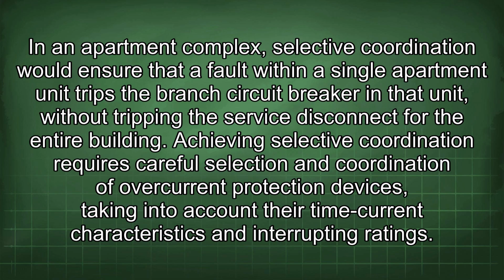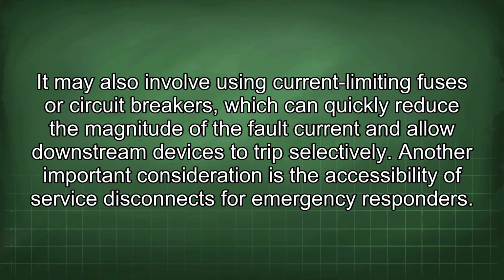Achieving selective coordination requires careful selection and coordination of overcurrent protection devices, taking into account their time current characteristics and interrupting ratings. It may also involve using current limiting fuses or circuit breakers, which can quickly reduce the magnitude of the fault current and allow downstream devices to trip selectively.